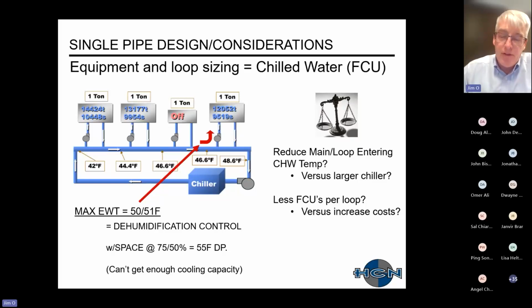So what are some ways to play with the water temperatures? One thing to think about is you can reduce your entering water temp, so in this case, to go from 44, say, down to 40. Just realize once you do that, you're increasing the work that your chiller has to do. Can you do it with the same size chiller, or do you have to go up a size? And then the other option you can think about is reducing the number of fan coils on each of the loops. Once you do that, you'd be increasing your first cost just because you're adding more piping mains, et cetera.